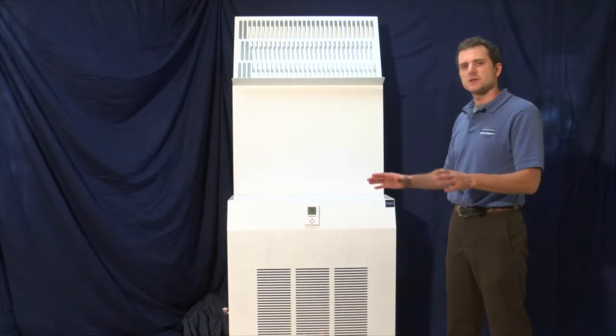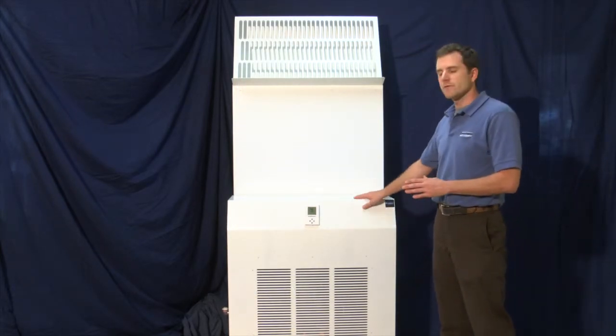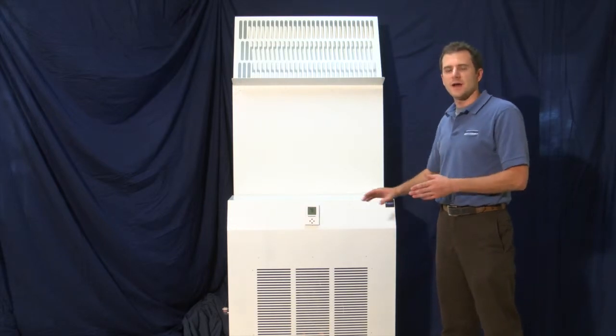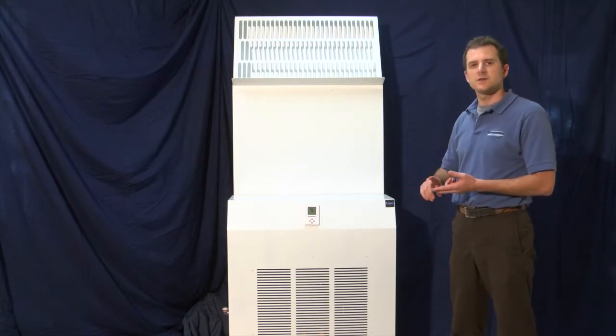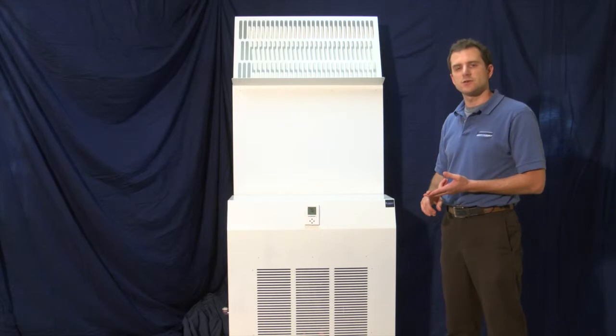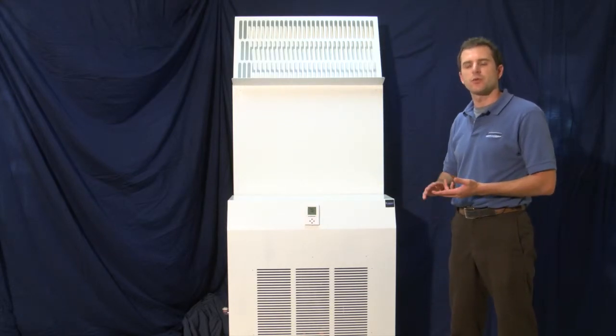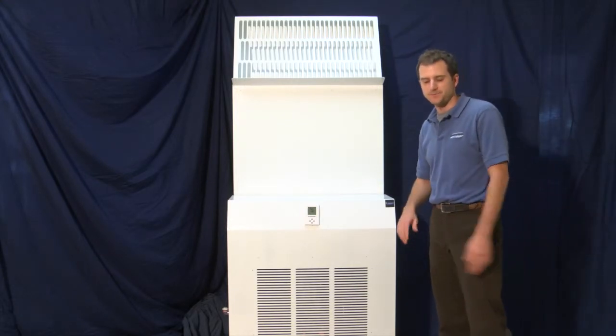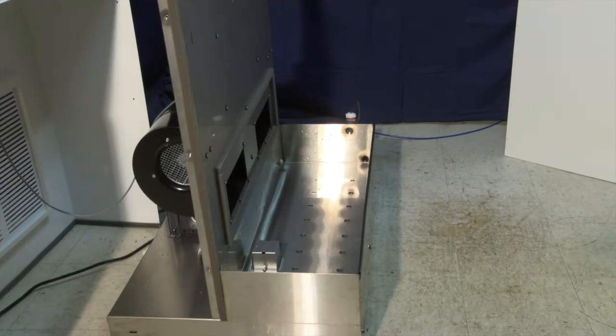An undersized water treatment system can starve the humidifier for water and not allow it to work correctly, and even in some scenarios damage the transducers because they're not allowed to operate with the proper amount of water on top of them. The best practice for ensuring the longest lifespan out of your transducers is to keep the water pan clean and clear of any contaminants.